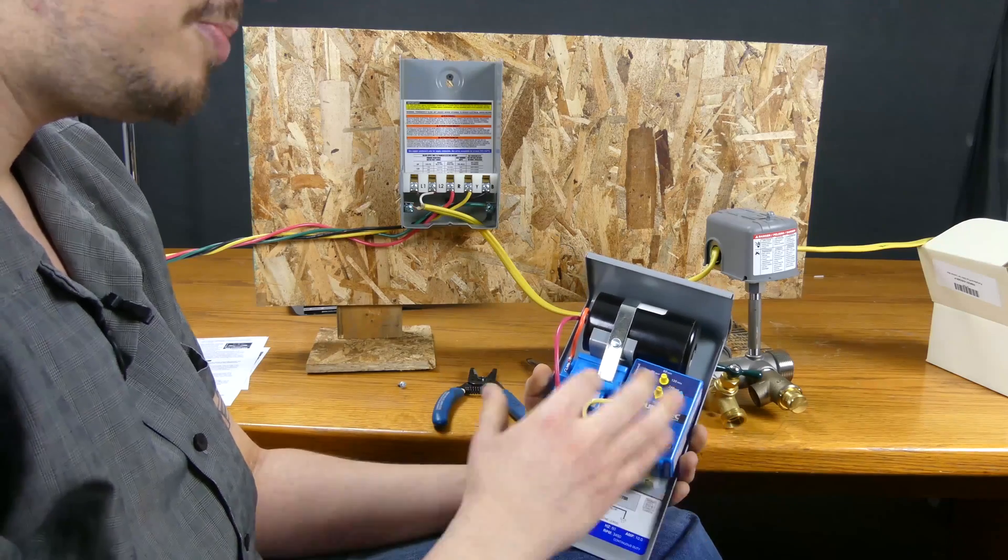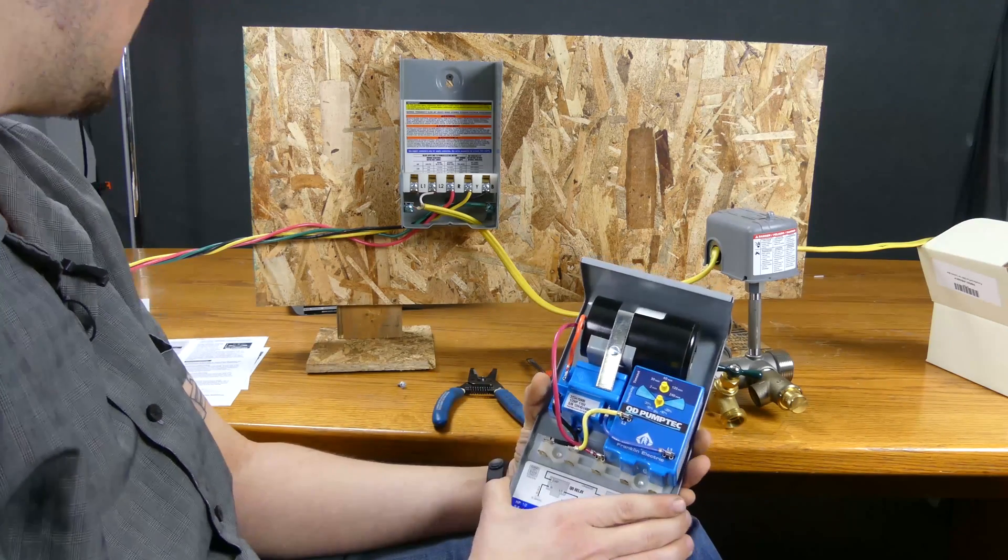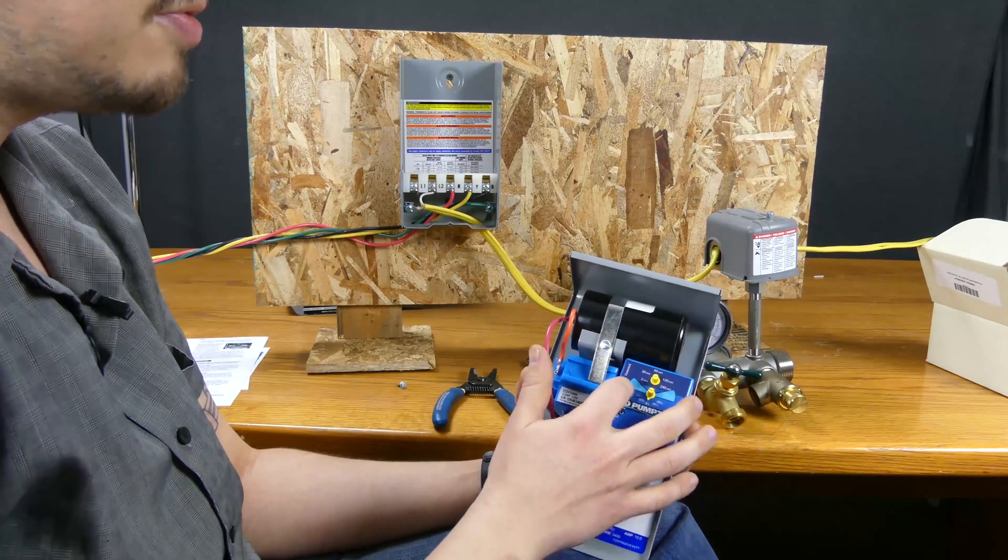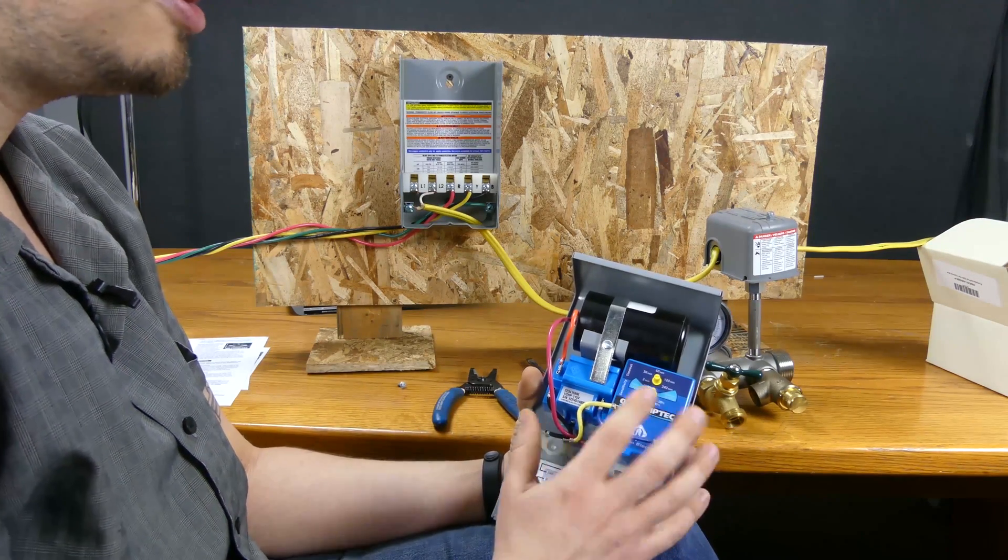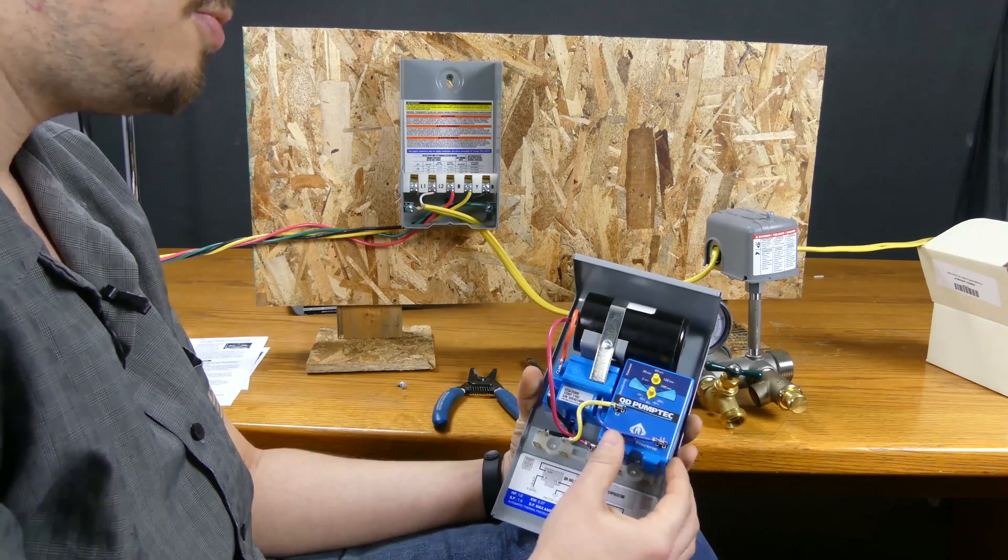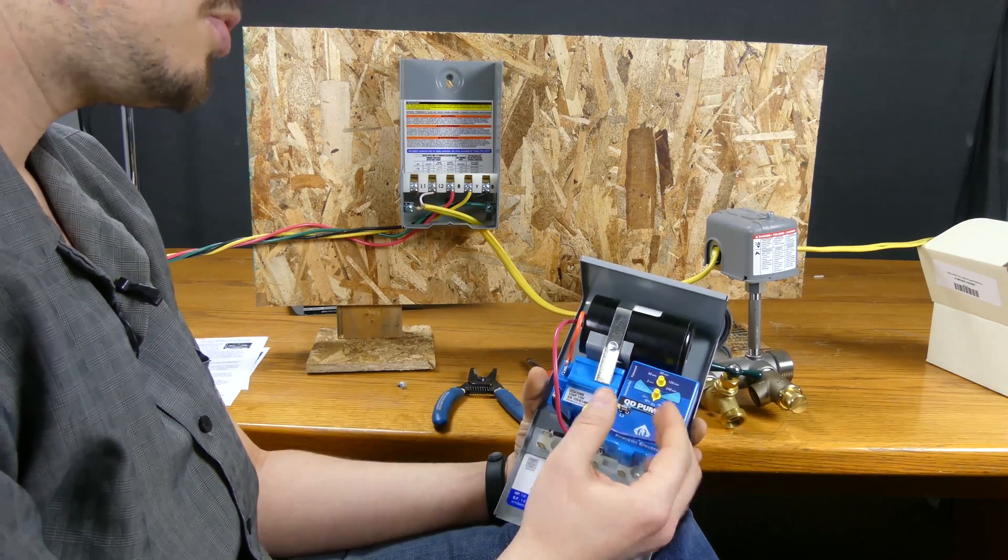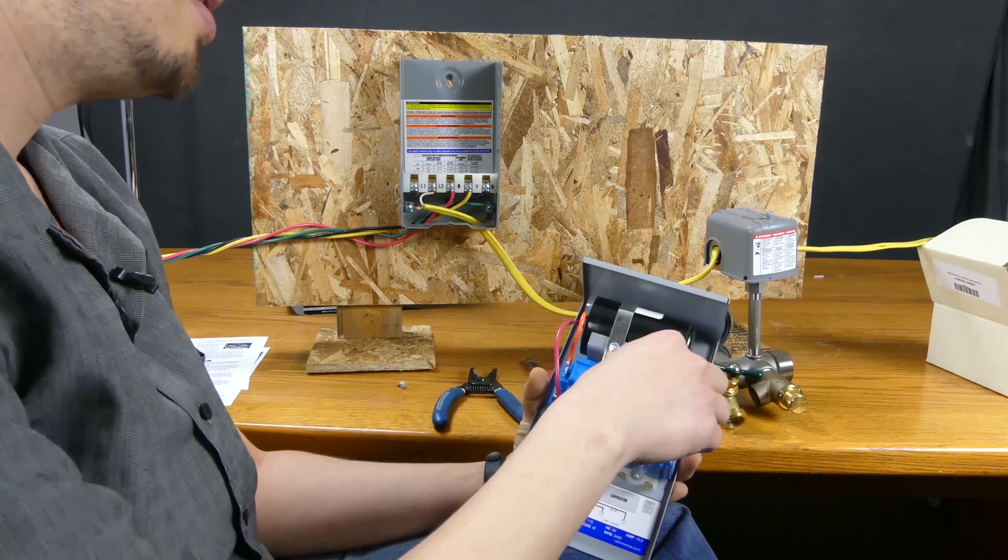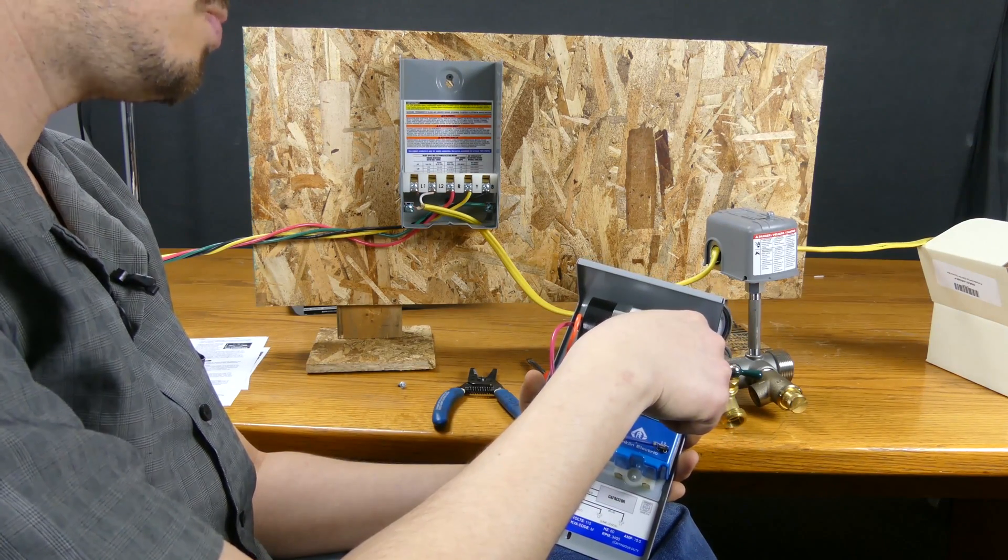Now there's really not a lot of need to mess with these sensitivity adjustments because this unit is designed to trip out at 80 percent of full load, so if your pump falls below 80 percent of full load. So if you want to reduce the sensitivity of that for instance...